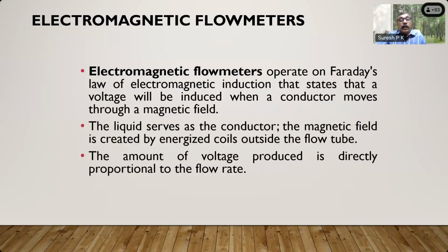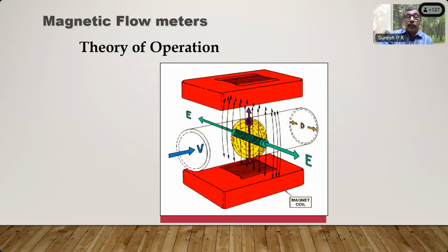Then another thing is electromagnetic flow meter, which is commonly used based on Faraday's laws of principle. That is, the liquid serves as the conductor and the magnetic field is created by energized coils outside the flow tube. The amount of voltage produced is directly proportional to the flow rate. Flow rate means the velocity. As the velocity increases, magnetic field, energized coils, it creates more voltage. This is the theory of operation. Magnetic coil is basically Faraday's law.